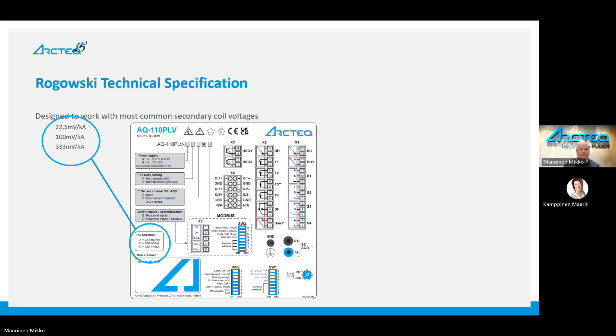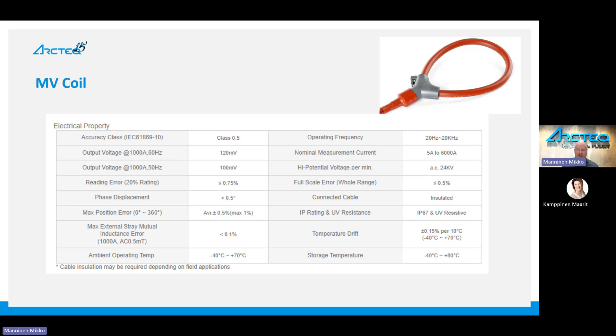A couple of slides back, you saw the LV version Rogowski sensor, and this is an example of the medium voltage sensor. This particular one is working with 100 millivolts per 1 kiloampere when it is 50 hertz. So it fits ideally with the medium voltage relay version.